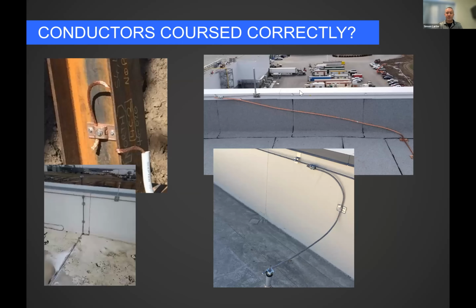Are the conductors coursed correct? On the right-hand side pictures, yes, the conductors are coursed correctly. They have a gentle upward slope to ground right there at the top. They have nice smooth bends, a nice sweep radius there. But then on the left-hand side, on the bottom, you've got conductor coming straight up the wall to ground. And then at the top, you've got the conductor making a big U-loop. The bend radius is too tight. It's making a 180-degree turn. It's also, if you look in the bottom right there, right by the conduit, kinked right over that I-beam flange. So that's just absolutely not cool.